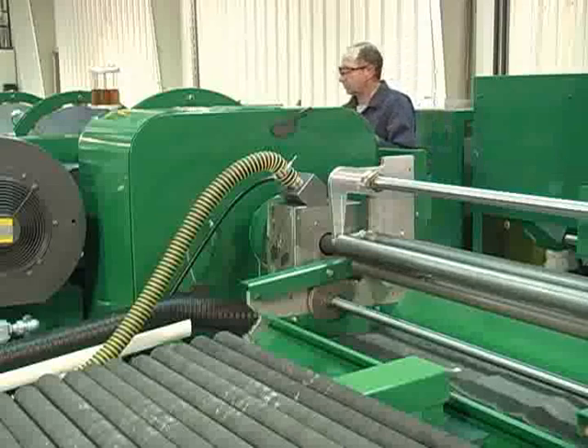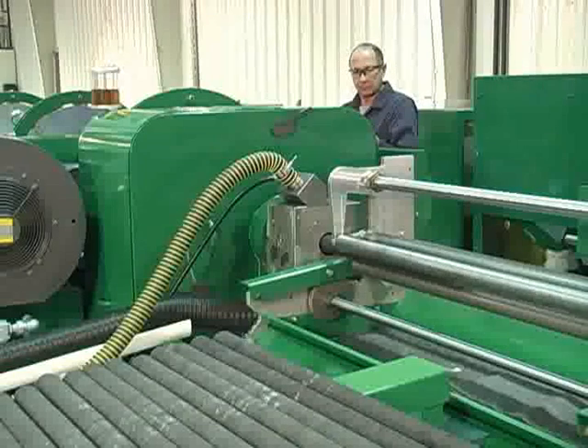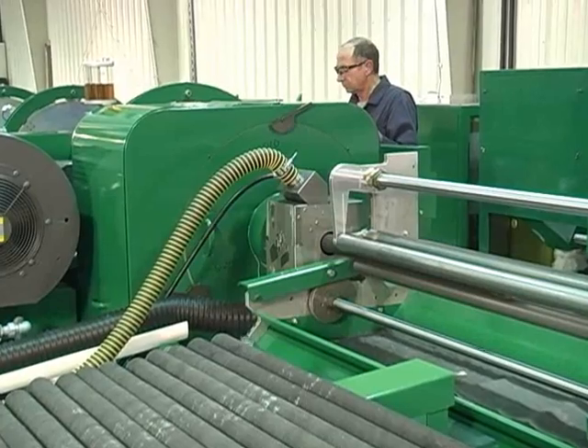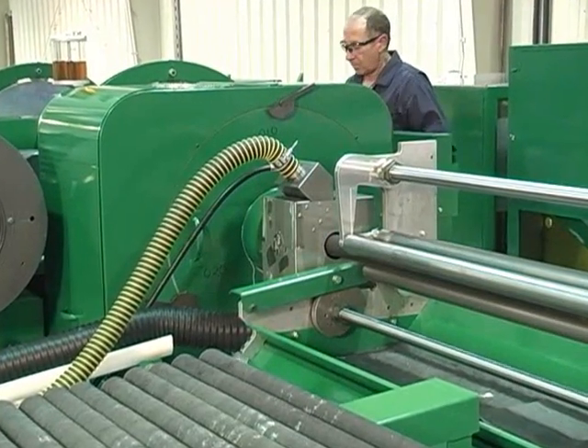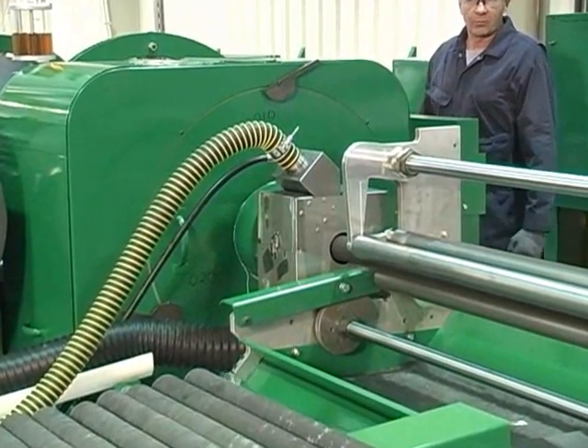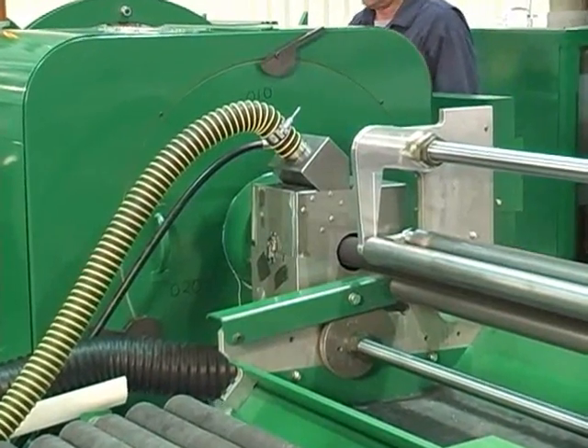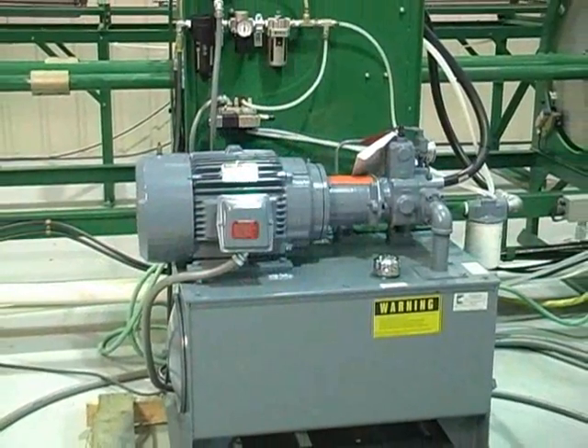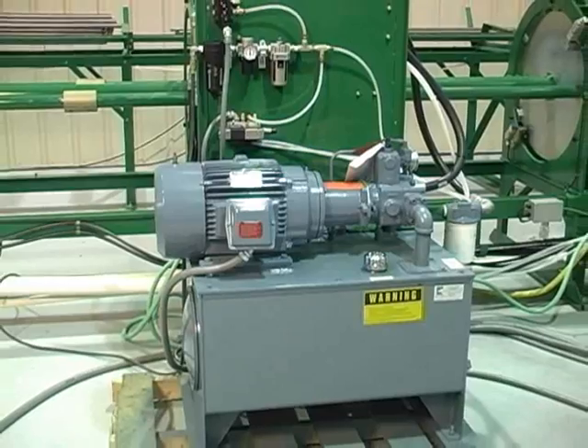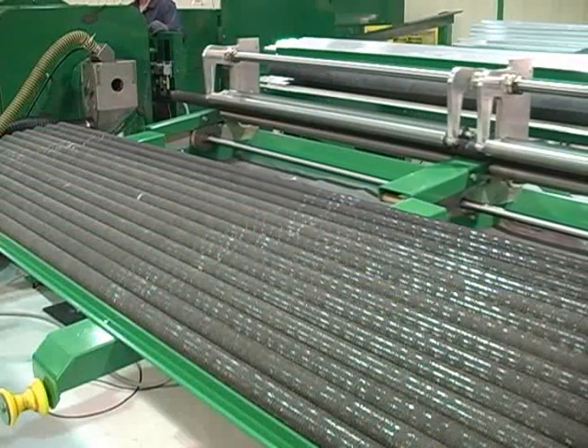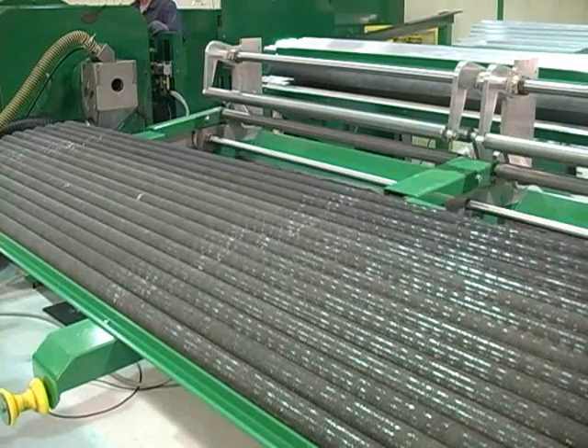Maximum productivity of a 1-inch tube with 10 FPI at 2800 RPM is 30 feet or 9 meters per minute. Anticipated annual production is 1.5 million feet in a single shift. Because of this unique design and arrangement developed by McElroy, the unit is able to operate on a continuous basis without the necessity of stopping to reload after each finning operation.